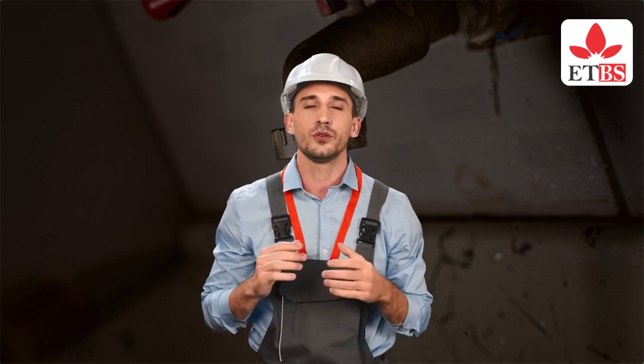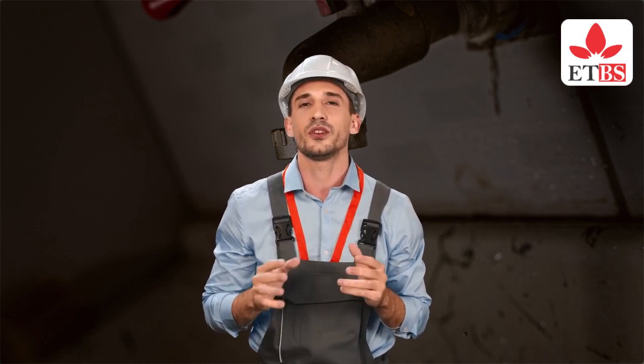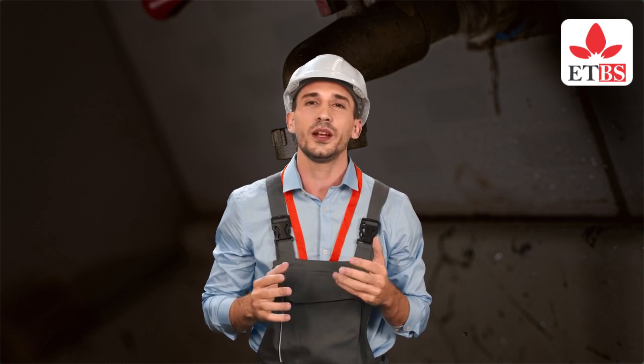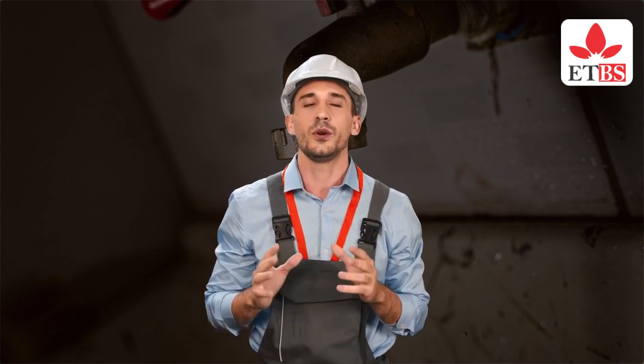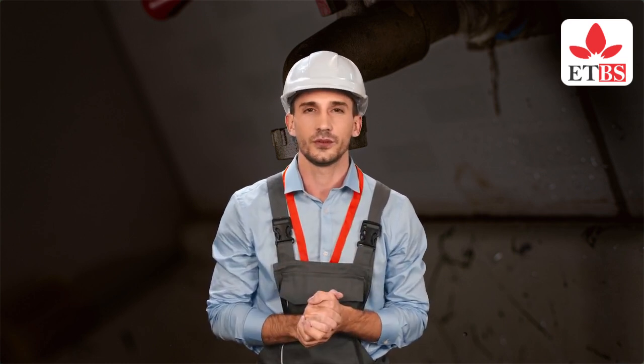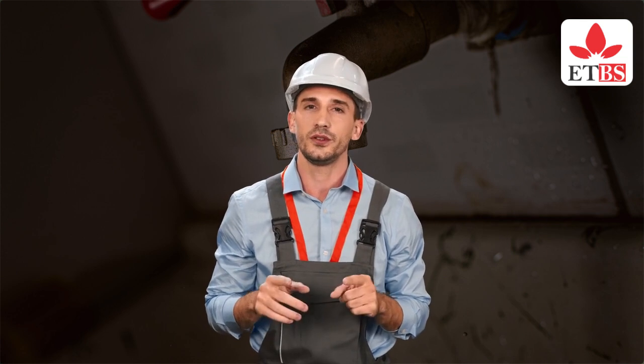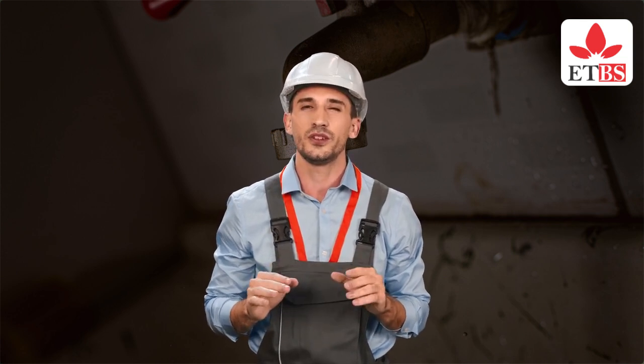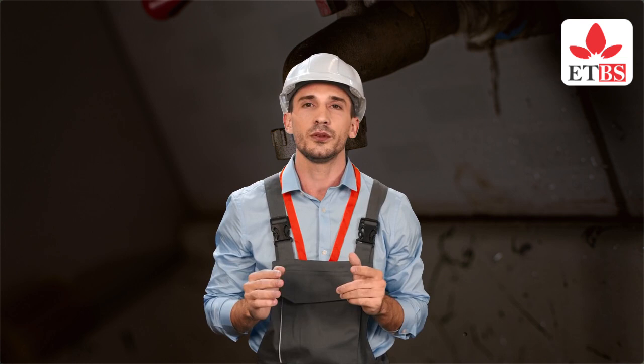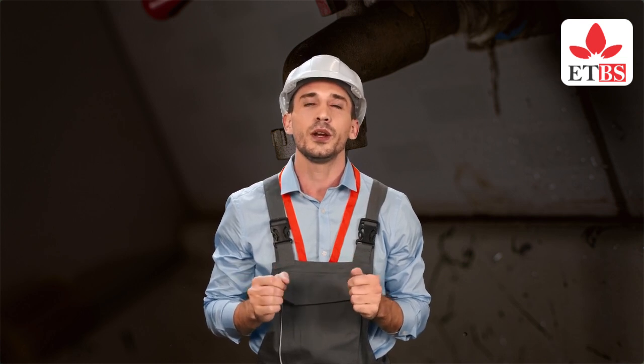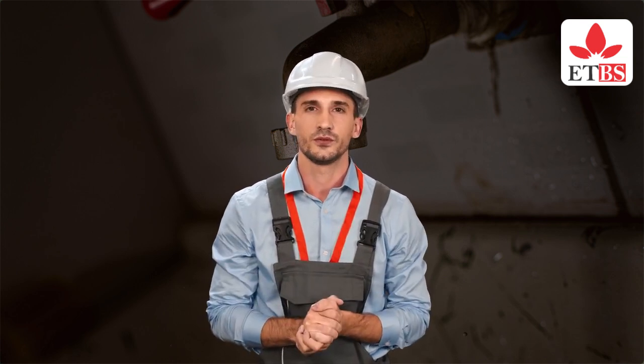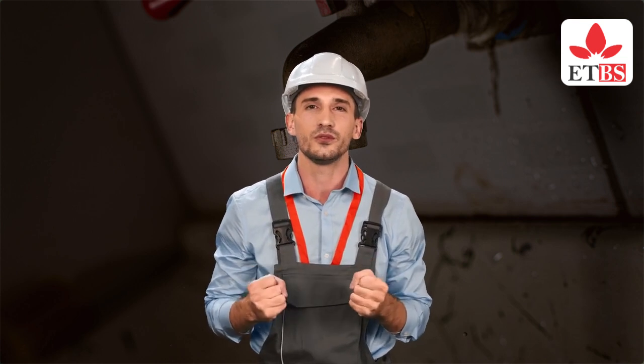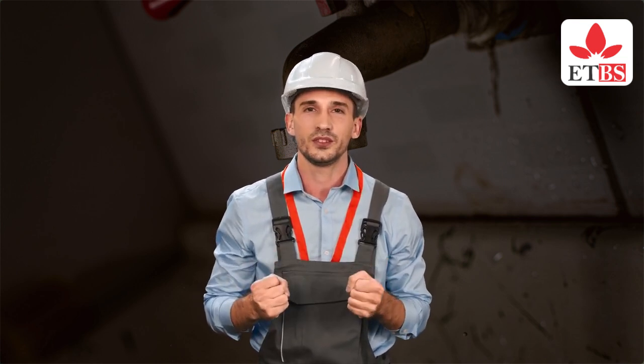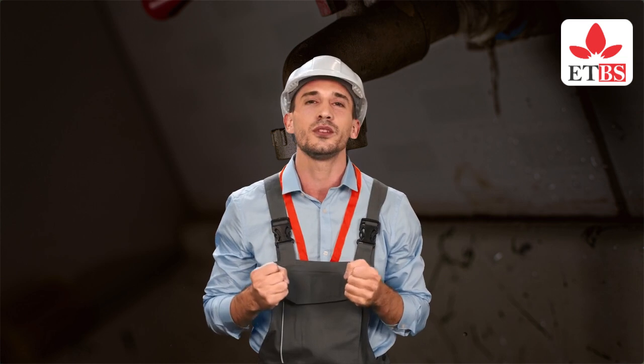6. Common drainage problems and troubleshooting. Blockages due to grease, hair, food particles, or foreign objects. Solution. Mechanical cleaning, rods, augers, chemical cleaning, hydrojetting. Foul odors caused by dried traps or poor ventilation. Solution. Refill traps, repair vent pipes, check seals. Backflow. Sewer water flowing back into fixtures. Solution. Install check valves and backflow preventers.